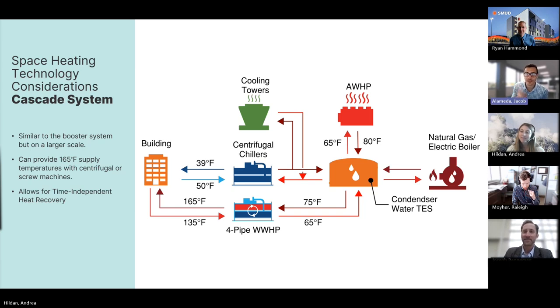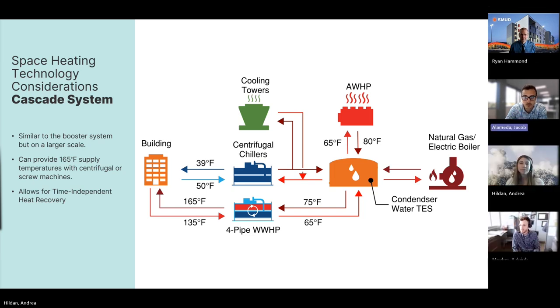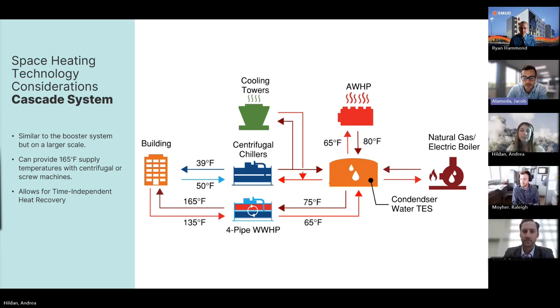Yeah, I'm going to try to hit all of those 5 sub questions, but if I miss one, definitely remind me. So the natural gas boiler. This is showing the centrifugal chillers, when they have load on them, they can reject their heat to the condenser water tank. When there's not chilled water load in your building, you don't have that heat to reject to your tank. And so that's the case where you would need trim heat. But say your building was a data center and you had all of the free heating that you needed from those centrifugal chillers because you have year-round load. It's cold outside, but you still have a ton of heat coming from servers in your data center. Those centrifugal chillers are still going to operate, and you're still going to have those chillers charging your condenser water tank. But if you're a typical office building or a school building where there's not that 24/7, 365 heating source from the chillers, then you probably have to use trim heating to get that heat source for your condenser water system.